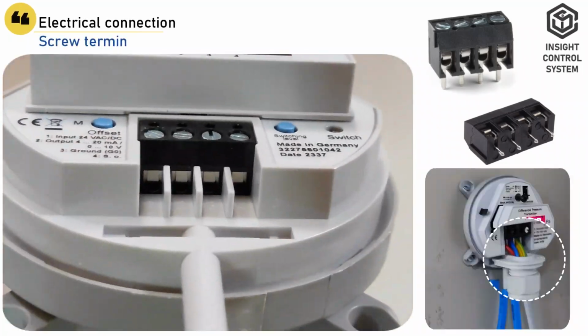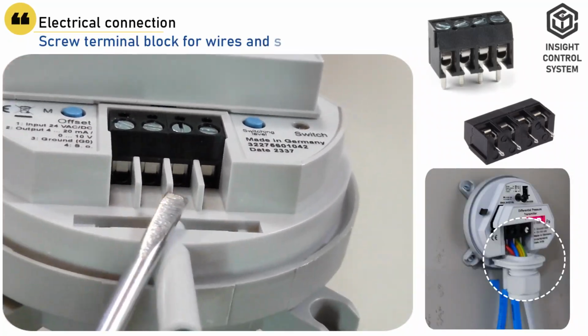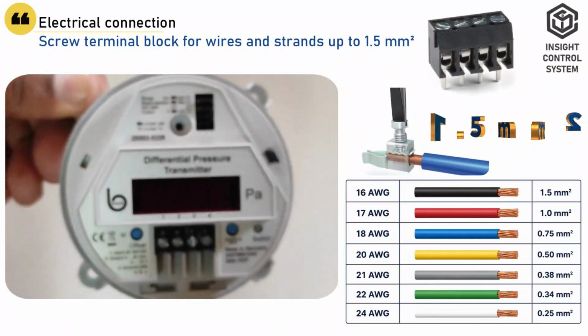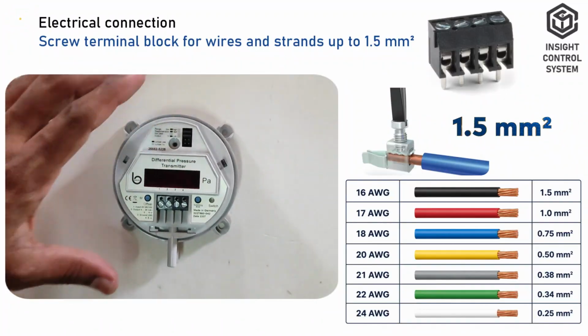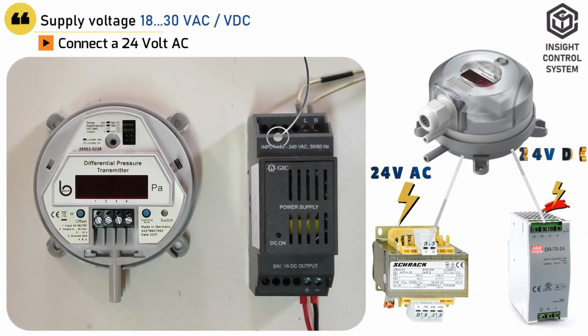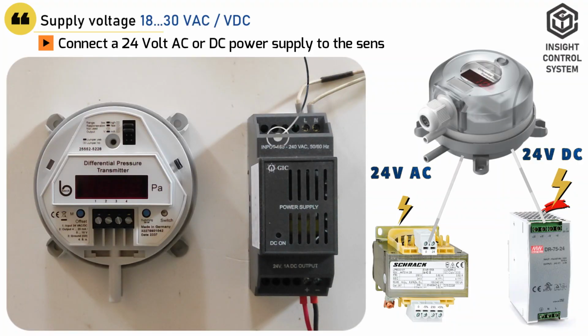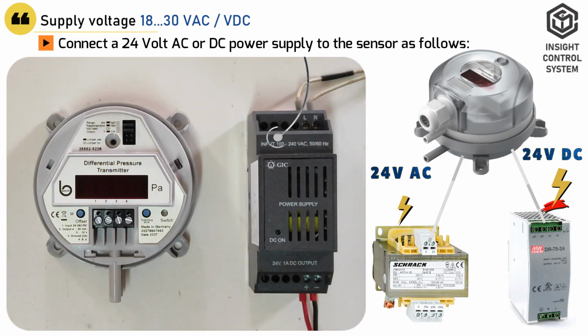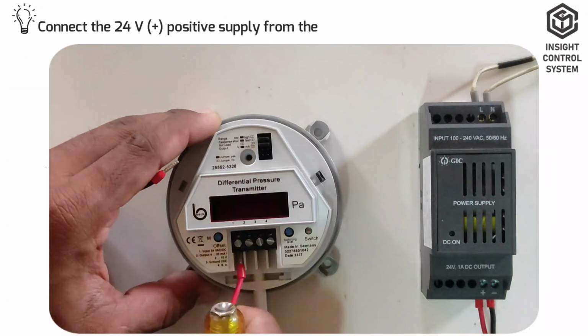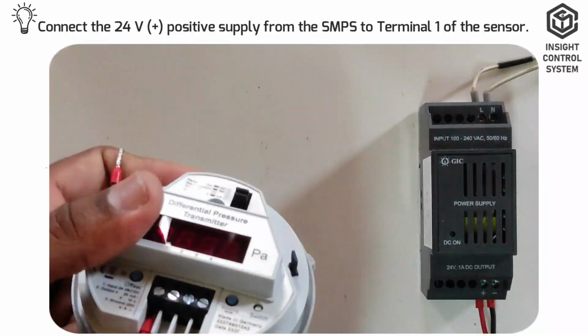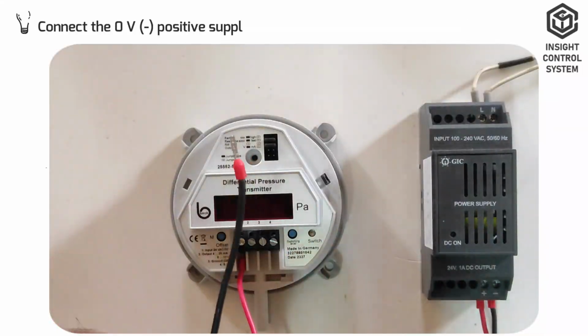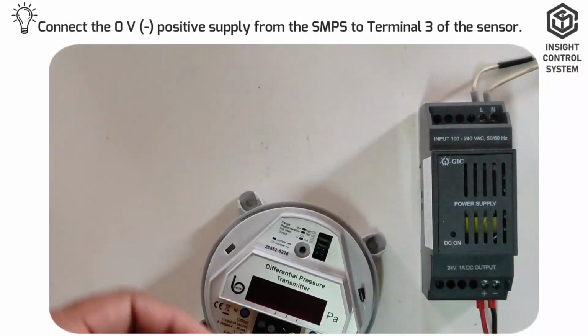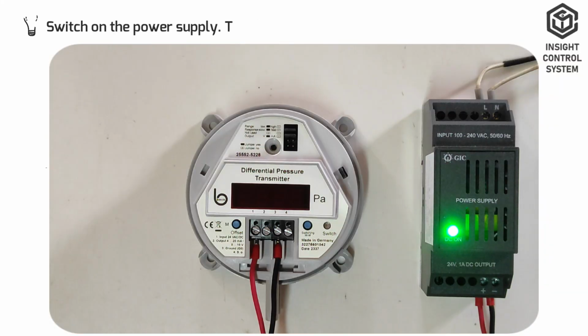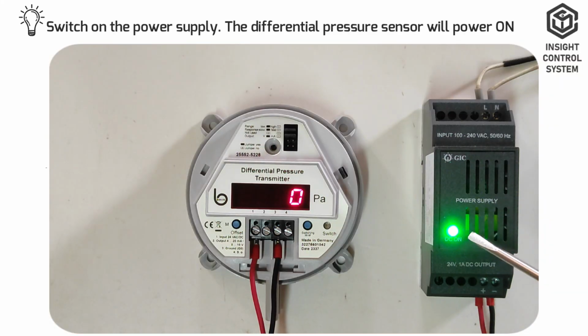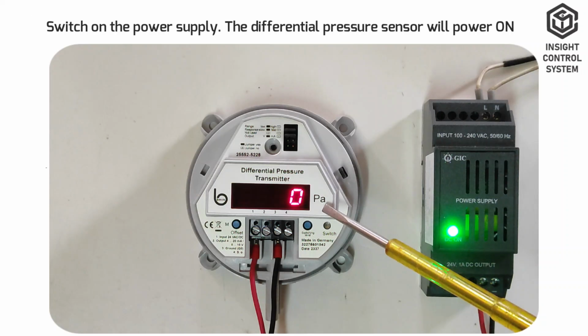The sensor has screw terminals for connecting wires or stranded cables with a maximum conductor size of 1.5 square millimeters. Connect a 24 volt AC or DC power supply to the sensor as follows. Connect the 24 volt positive supply to terminal 1. Connect the 24 volt negative supply to terminal 3. Switch on the power supply. The differential pressure sensor will power on.